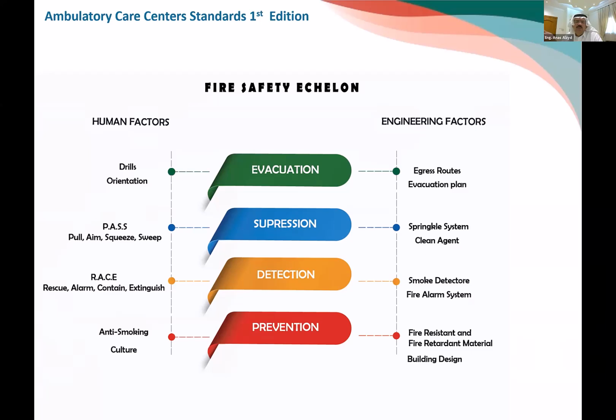I'm sure there are 20 or 30 times that fires were suppressed or contained by the people inside the building before even calling the civil defense because of detection. They either smell it or hear the voice. So please, detection is very important to contain the fire in the first 3 minutes. So keep it in your mind. A detection system, you want it to work in 3 minutes before they start. So all the system has to be ready and working.